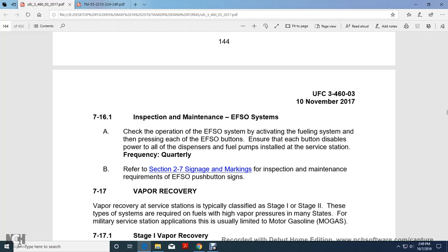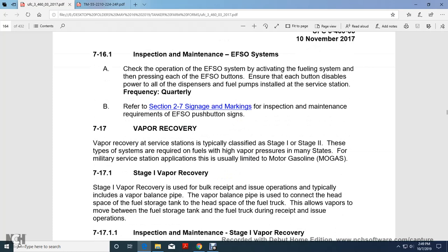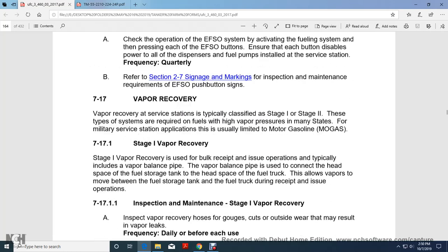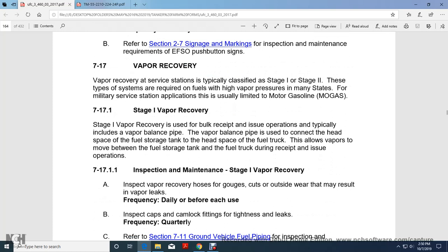Inspection of the emergency fuel shutoff. Check the operation of the emergency fuel shutoff system by activating the system and pressing the emergency fuel shutoff buttons. Ensure that each button disables the power to all the dispenser fuel pumps installed at the service station, quarterly. Refer to Section 27, signage marking, for the inspection maintenance requirements of the emergency fuel shutoff push button signs. 717 vapor recovery.